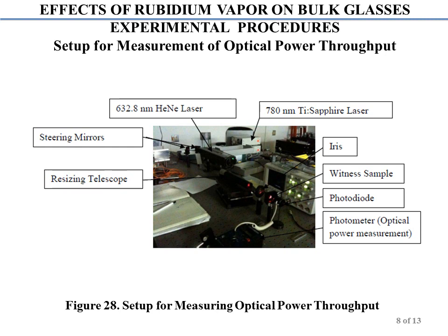An additional 26 measurements, minimum, maximum, and the average power transmission, were computed for each sample and taken at near field and far field, this time after passing through the optical window. The maximum power of the laser beam measured at either near or far field was less than 1 milliwatt for the 632.8 nanometer helium neon laser and less than 2 milliwatt for the 780 nanometer Ti sapphire laser, with a plus or minus 10% measurement accuracy.